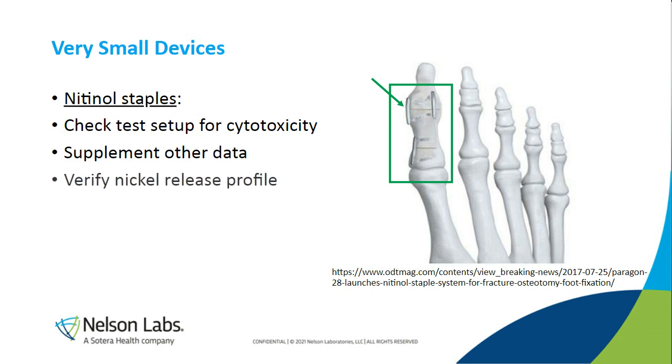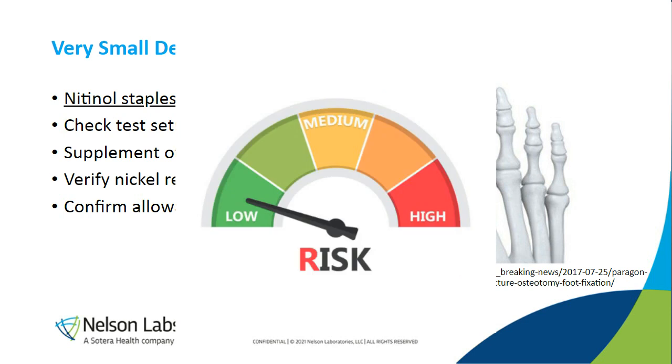But you can also use, for implantable devices, especially metal devices, usually we recommend having supplementary data anyway using chemistry, like through extractables and leachables testing, so you can use that data to supplement this question as well. So in this case, we were also able to confirm that the amount that was coming out of these nitinol staples was much lower than the allowable levels allowed by the standards or the guidance documents, and we were able to prove again that the risk of the nickel release in the clinical use scenario was low.